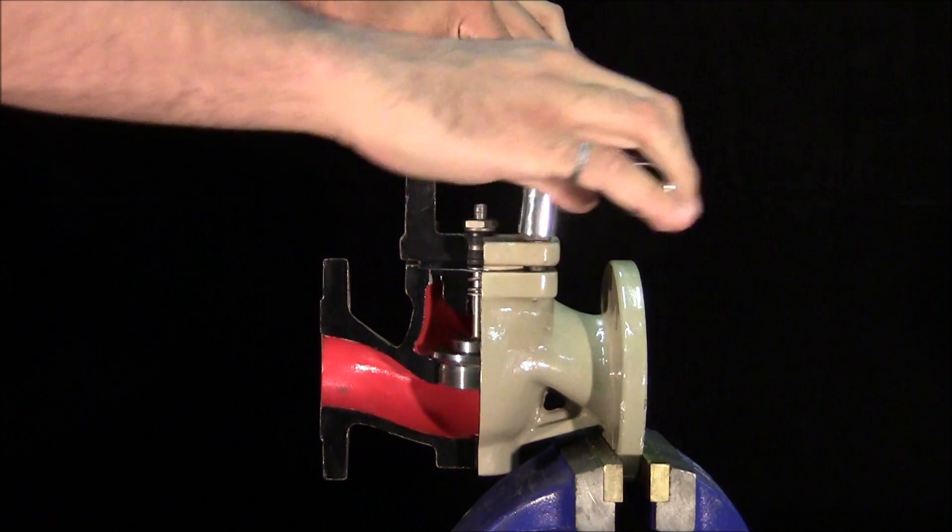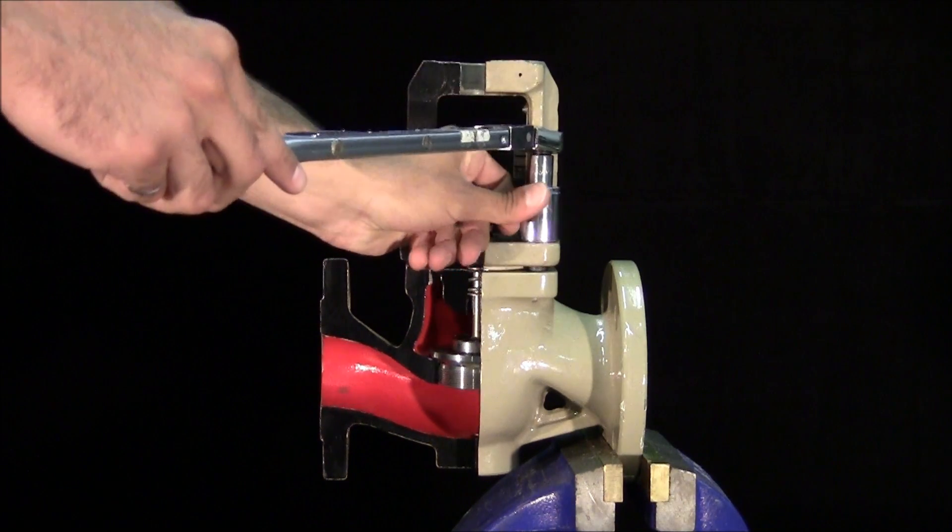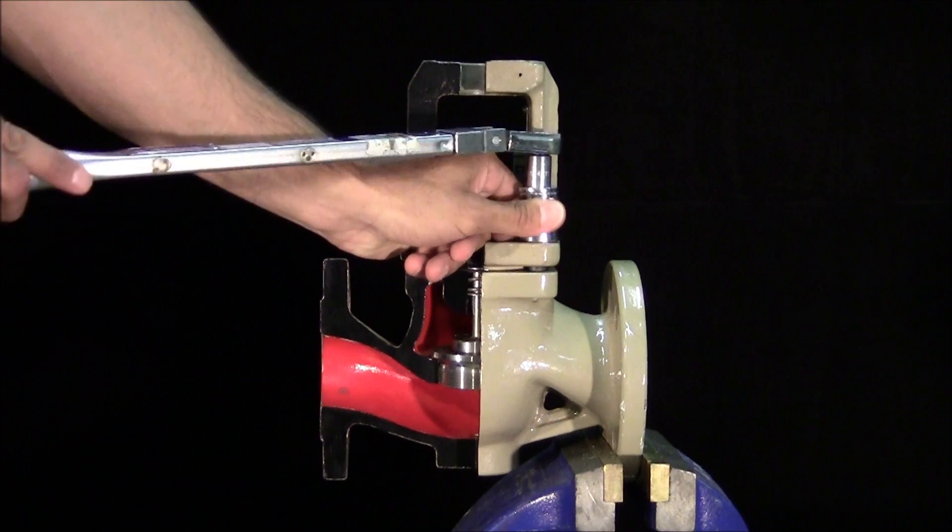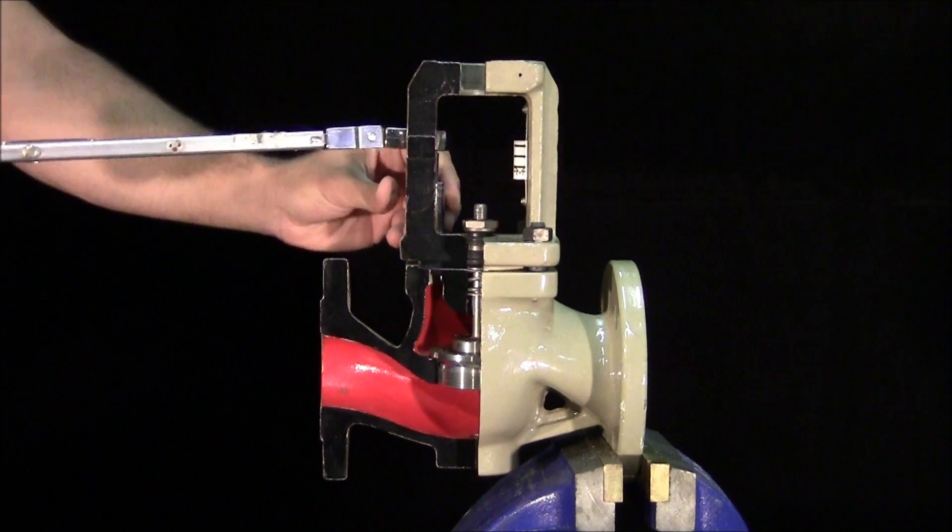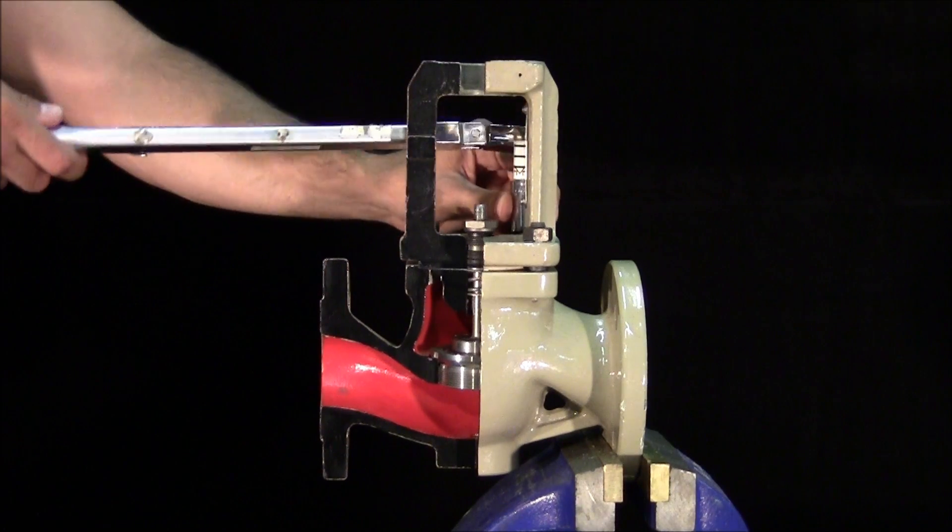A torque wrench will be used to tighten the nuts. In a criss-cross fashion, tighten to 50% of the torque value and then again to 100%.